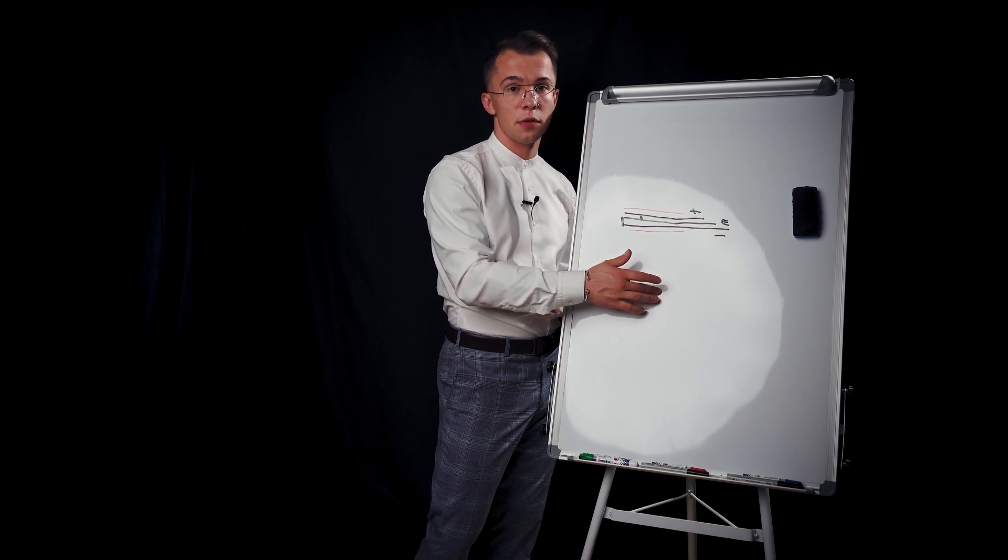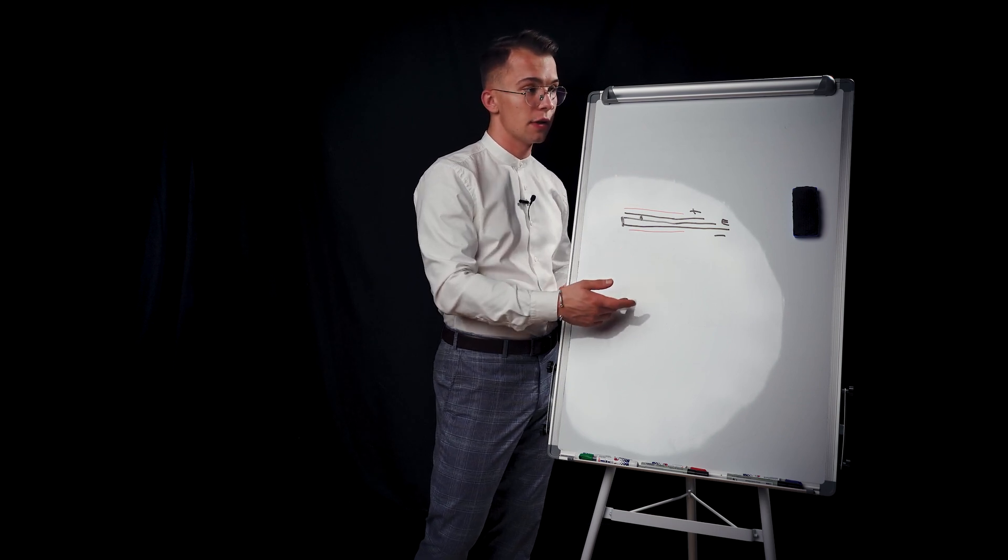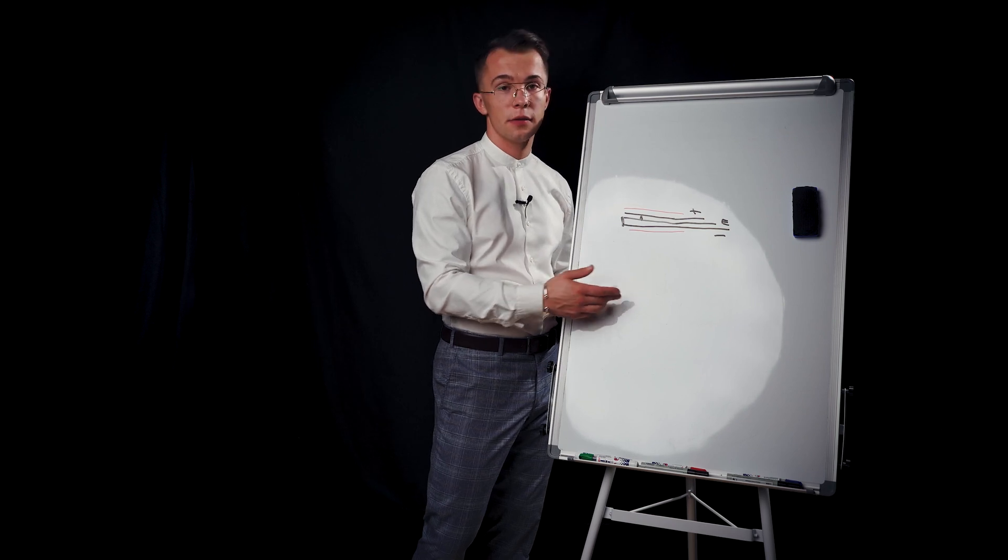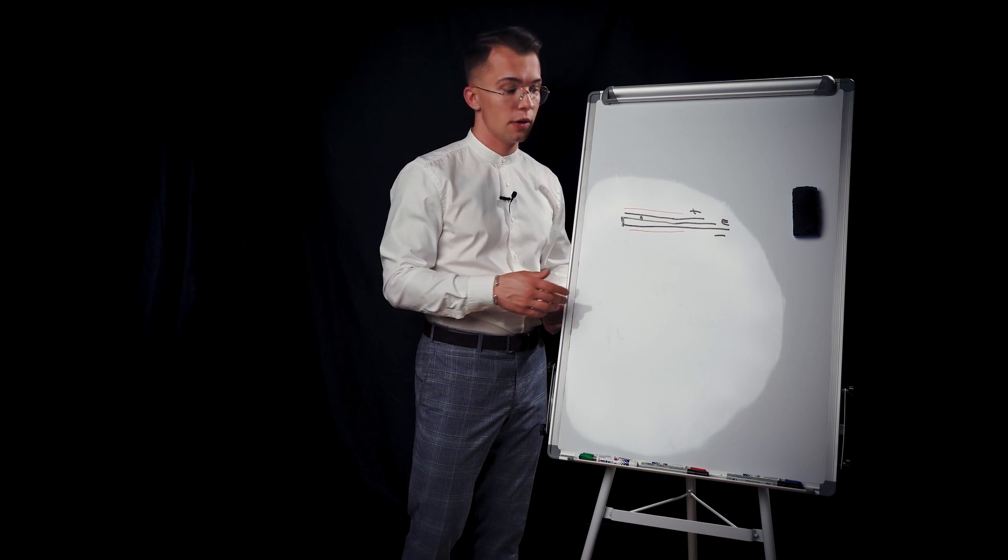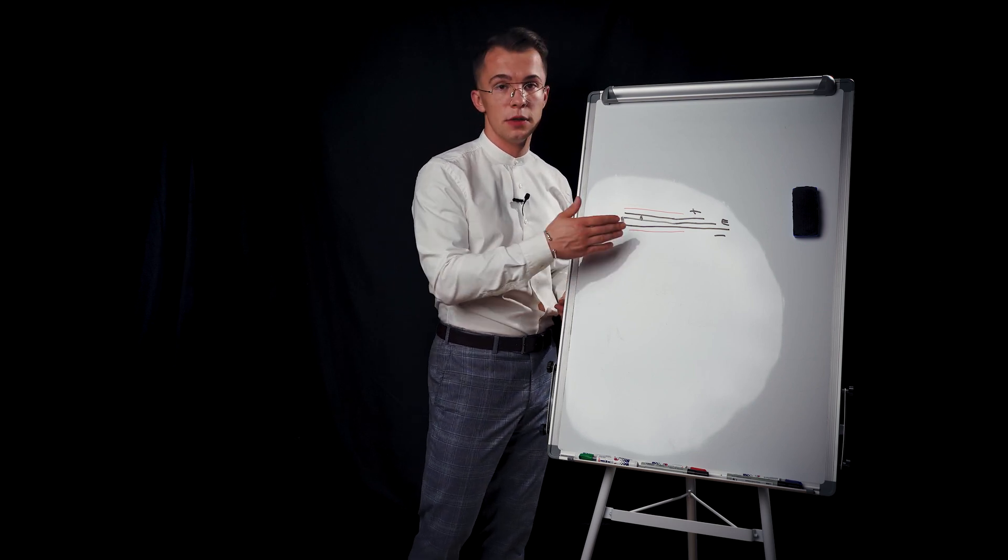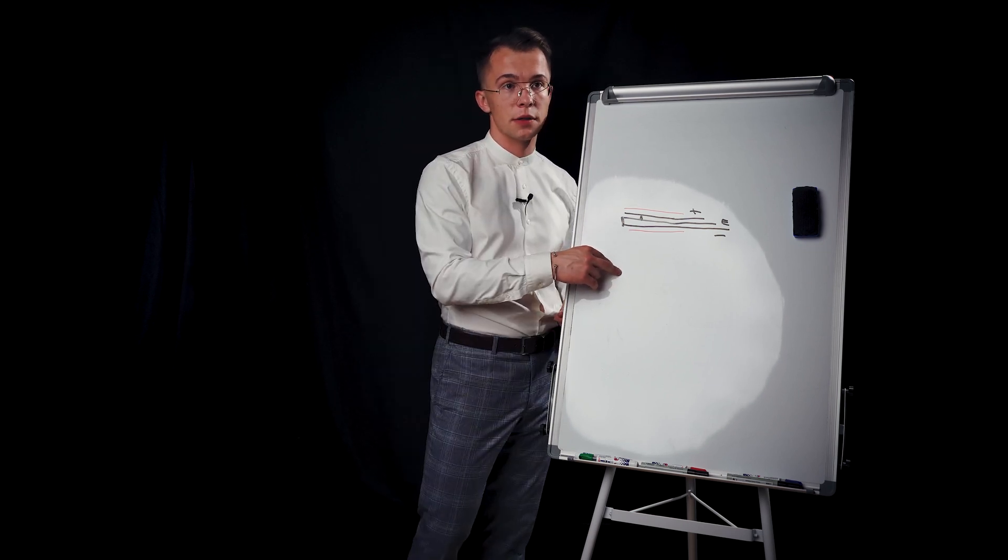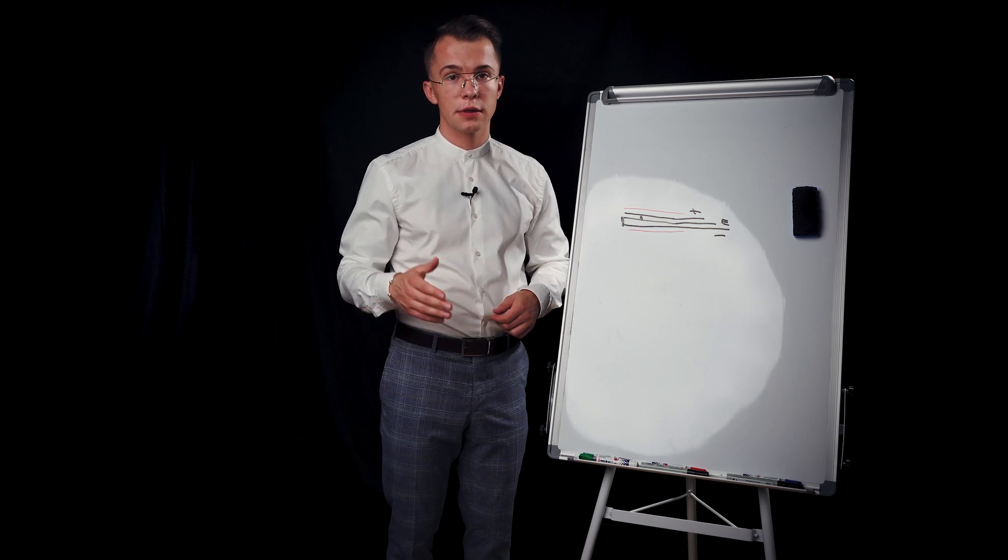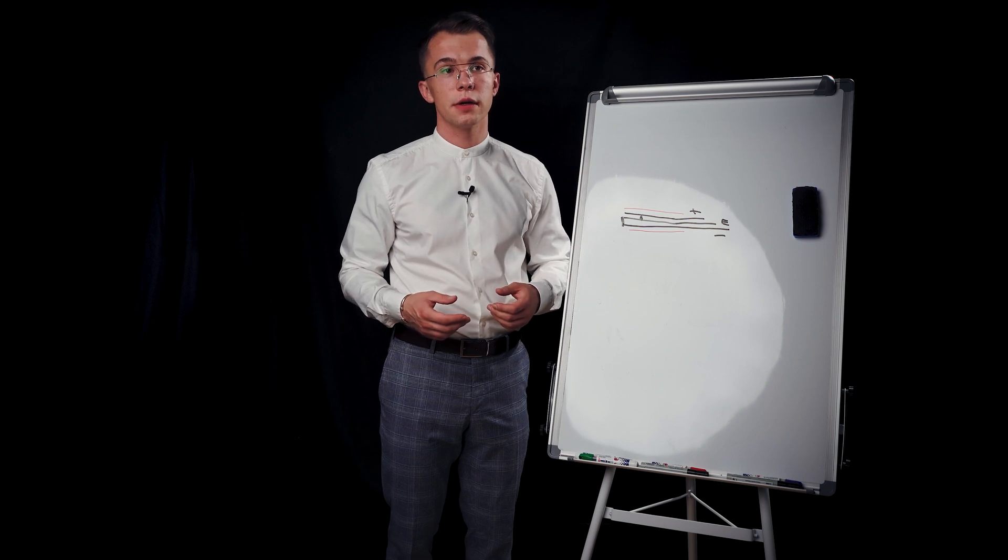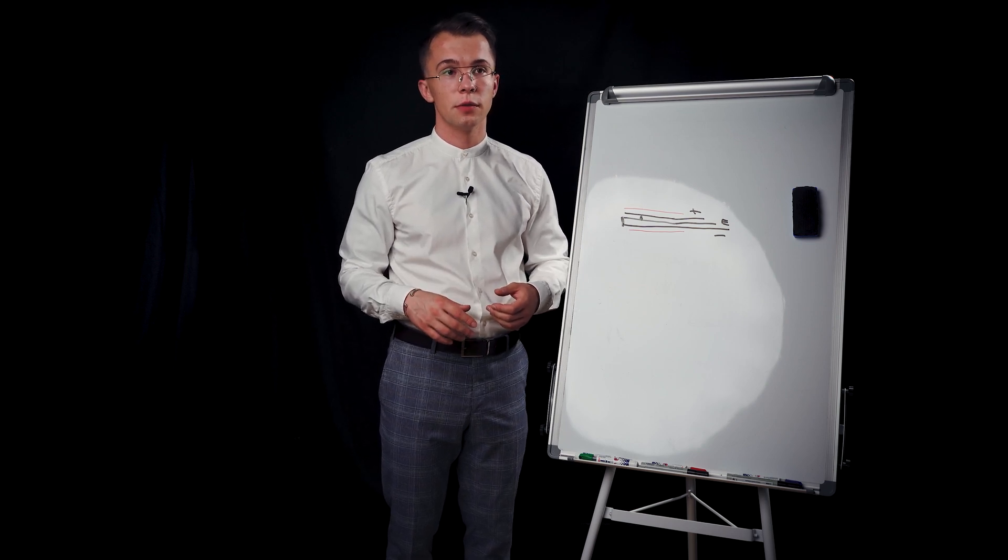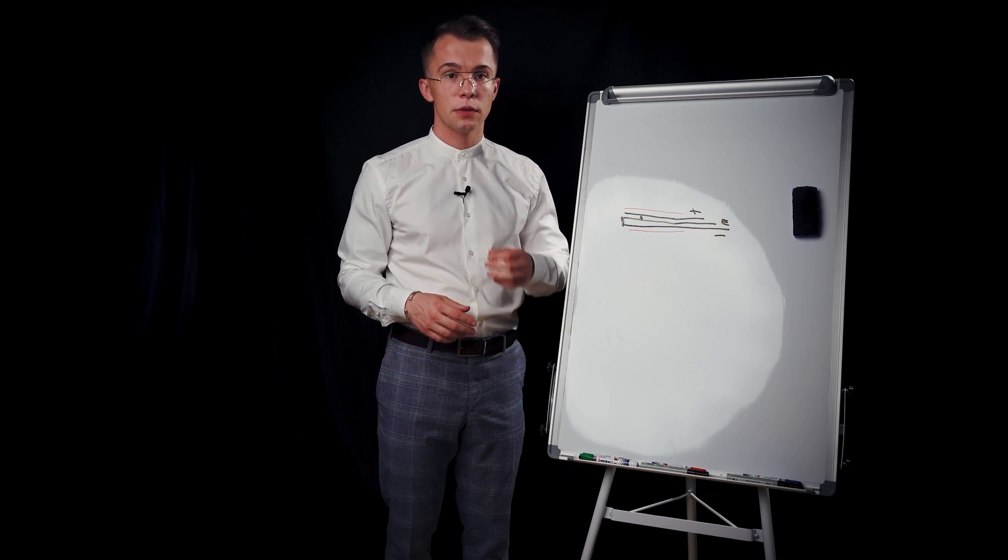If you find that, let's say, the left side is causing the problem, you're going to split this left side of the loop in half again and see if the problem remains. That way, by splitting and connecting to the panel, you'll be able to find roughly the point on the loop where this earth fault might be.